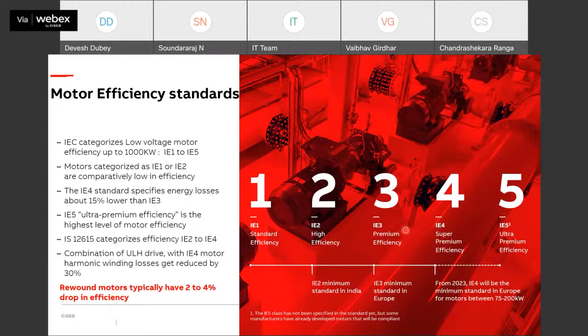Nowadays we see rewinding of motors is a general phenomenon in the steel industry and cement industry. One time if you rewind the motor, it will drop the efficiency by 2 to 4%, and every time you rewind it, the efficiency comes down. As experts, we always advise it is better to replace the motor with a higher efficiency motor.